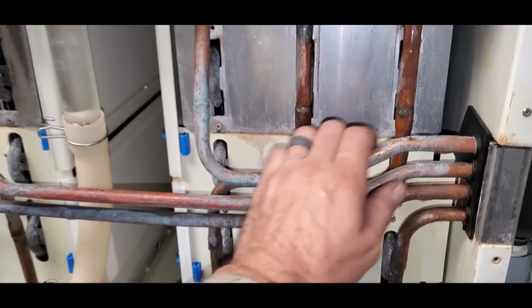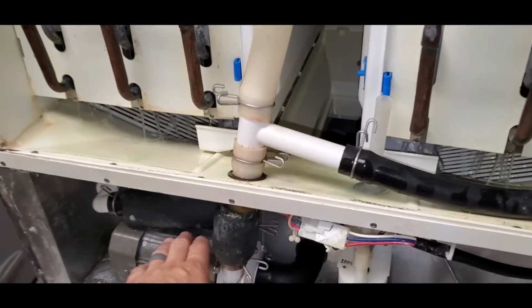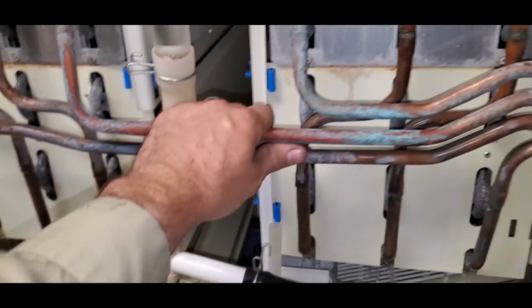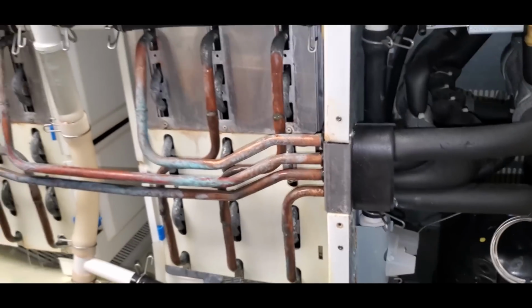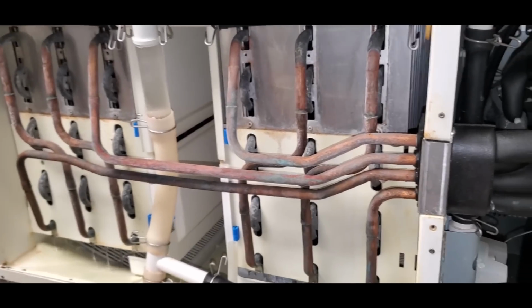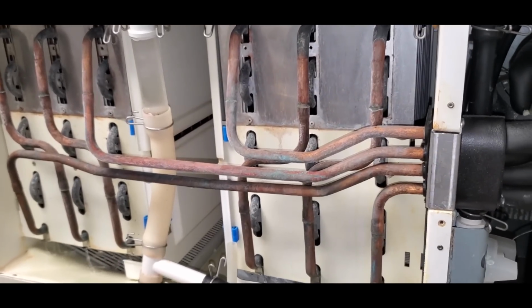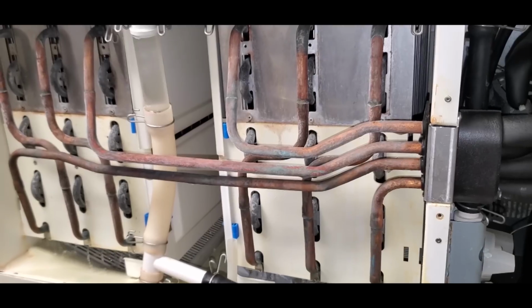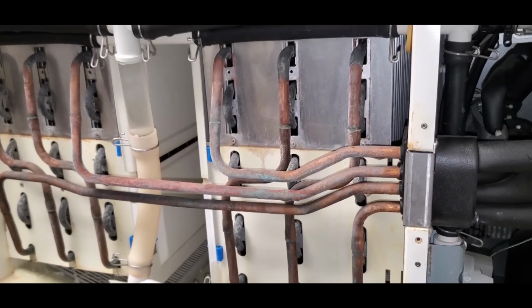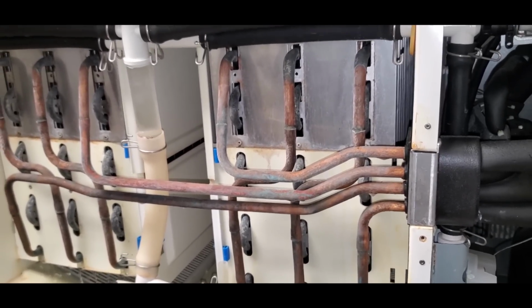Alright, so the hot gas valve turned off, and the water pump's now running, so we'll start our timer. At the 5-minute mark we'll check our pressures. We're looking low on head pressure, but our suction pressure is kind of on point, which is a little disconcerting because I'd like to see both of them low to really validate a low refrigerant charge.